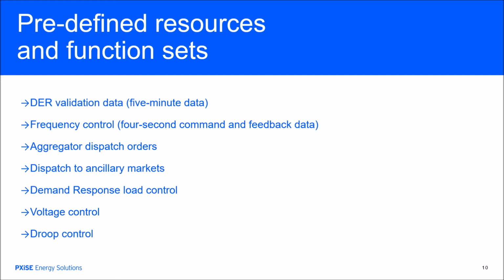In the standard, if you read it carefully, you'll see there's really no defined standard for what the time interval should be. Several of the examples show sending messages every 15 minutes. But at Oslo, we chose to run the controls every 5 minutes. There's nothing to prevent us from running that protocol in 4-second intervals or even faster.